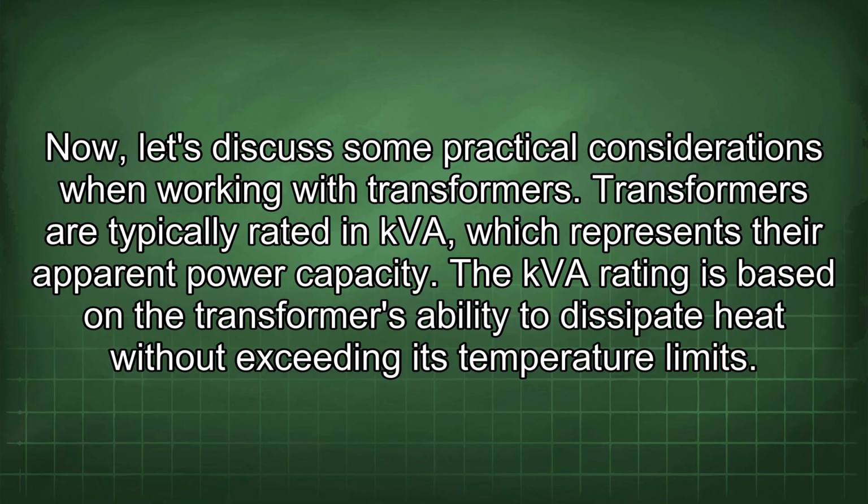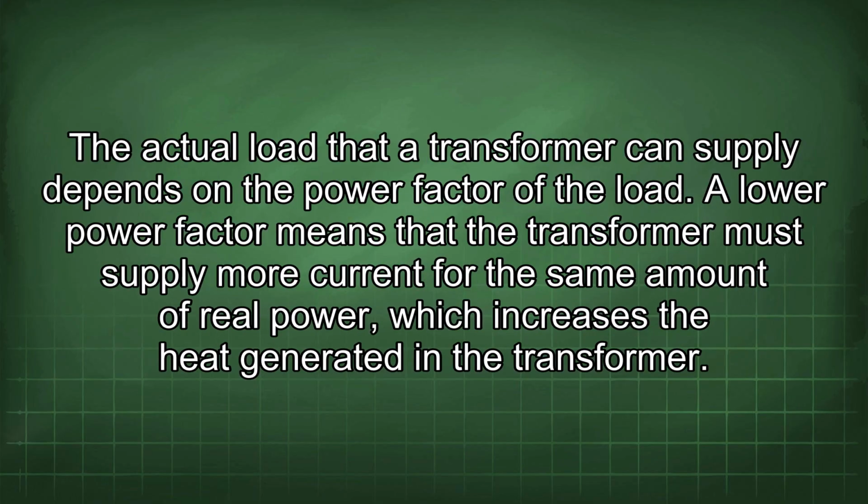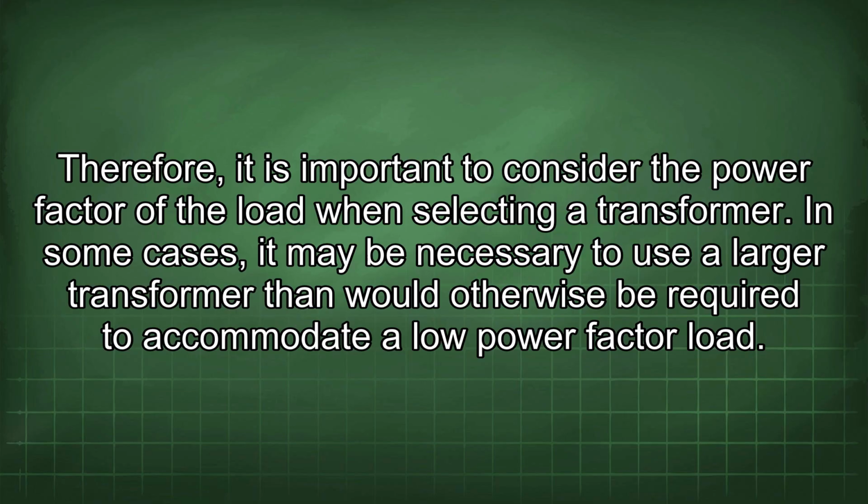Now let's discuss some practical considerations when working with transformers. Transformers are typically rated in kVA, which represents their apparent power capacity. The kVA rating is based on the transformer's ability to dissipate heat without exceeding its temperature limits. The actual load that a transformer can supply depends on the power factor of the load. A lower power factor means that the transformer must supply more current for the same amount of real power, which increases the heat generated in the transformer. Therefore, it is important to consider the power factor of the load when selecting a transformer.